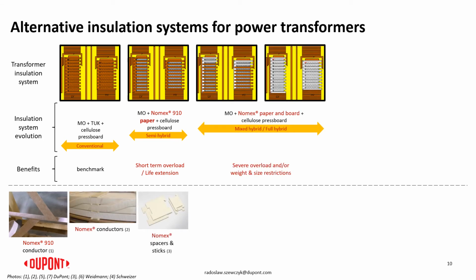Then we could talk about more advanced systems like the hybrid systems mentioned on the previous slide. So that could be a mixed hybrid system or the full hybrid system. They already allow quite severe overload and also the weight and size reduction in the transformer. So whenever the space or the weight is a constraint, like in case of mobile transformers for emergency, these solutions of hybrid insulation systems are popular in that type of transformers.